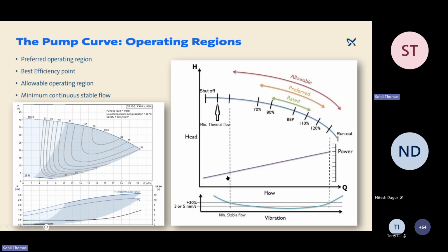Also, you can see this dotted line over here. If the flow goes below this, there is a minimum continuous stable flow that every pump needs. And if it goes below that, there is a thermal flow that's going to create a cavitation effect throughout the pump, and that's going to damage the impellers and other components within the pump system. So the main idea is to operate around the BEP, and to do what it takes to make sure we operate around that region and within the rated or preferred region that you see on the screen.